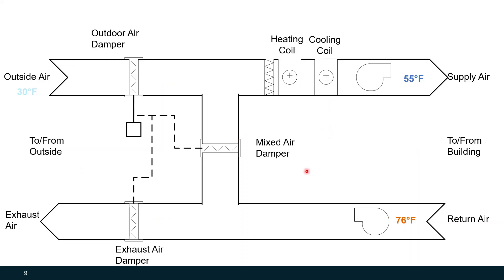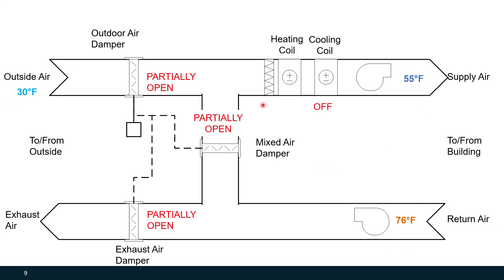Now let's say it's a slightly colder day — 30 degrees outside. We might want to use some return air because that's at 76 degrees, but because the building is still in cooling and maybe we have a lot of internal load, we still want to supply 55 degree air. We can actually mix the return air and outside air streams to get exactly 55 degrees, and our cooling coil can stay off — and so can our heating coil. So our dampers have modulated to achieve a mixed air temperature of 55 degrees.